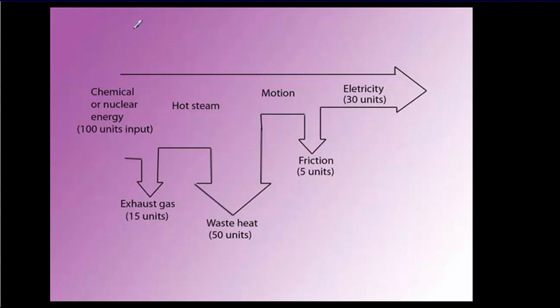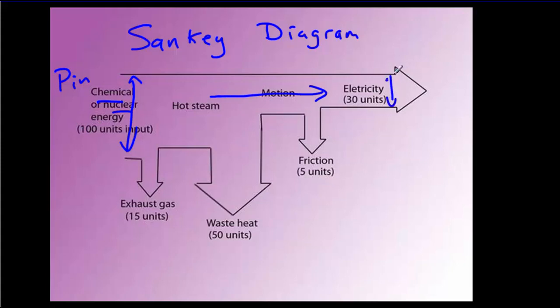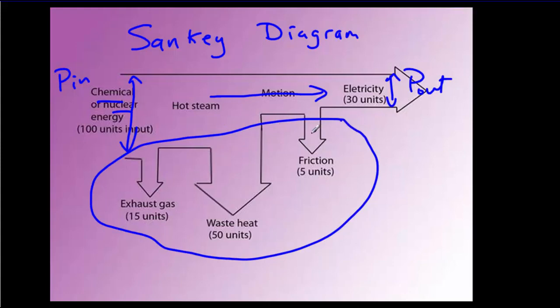The representation below is called a Sankey diagram. And this one's for a chemical or a nuclear power plant. And what we represent here, this width on the left-hand side, that would be the input power. That's the energy that's available from our nuclear fuel. And if we go straight across here, this width here represents the output power or the electricity that we're producing. That's the good stuff that we want. And then over here, this is all the thermal energy that gets lost along the way. So we have friction because of the water flowing through the tubes. And we have exhaust coming from the extremely hot fuel chamber. And the big one, though, is this waste heat that's occurring at the condenser. So a power plant is a cyclic process and can never be 100% efficient and is very seldom over 50% efficient. Even the best natural gas plants are only about 50% efficient. So this energy here is quite large.